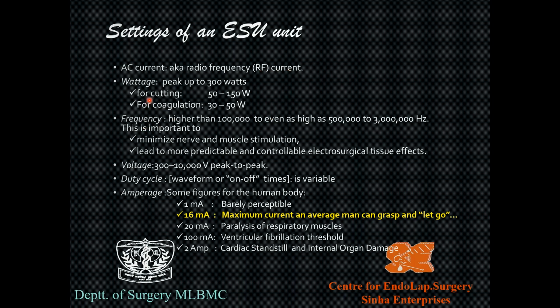The wattage is one of the important parameters you should remember. It peaks up to 300 watts - meaning it can deliver 300 watts of power when you're pressing the pedal. But for cutting, an ideal range is 50 to 150 watts, and for coagulation, 30 to 50 watts is required and enough. You never require a 300 watt output.